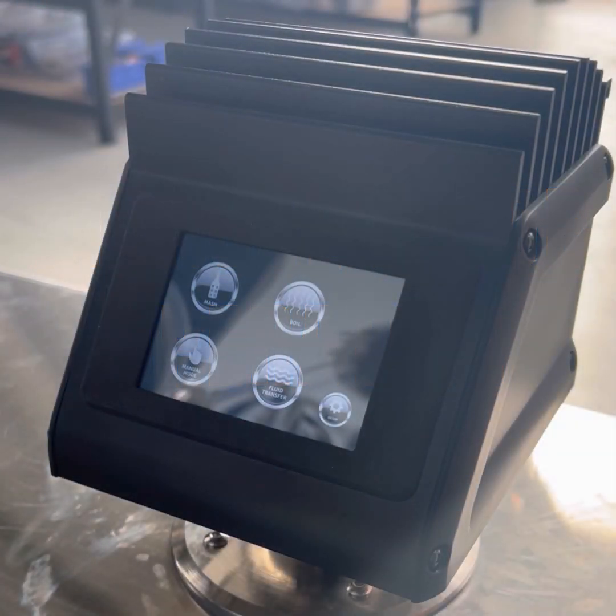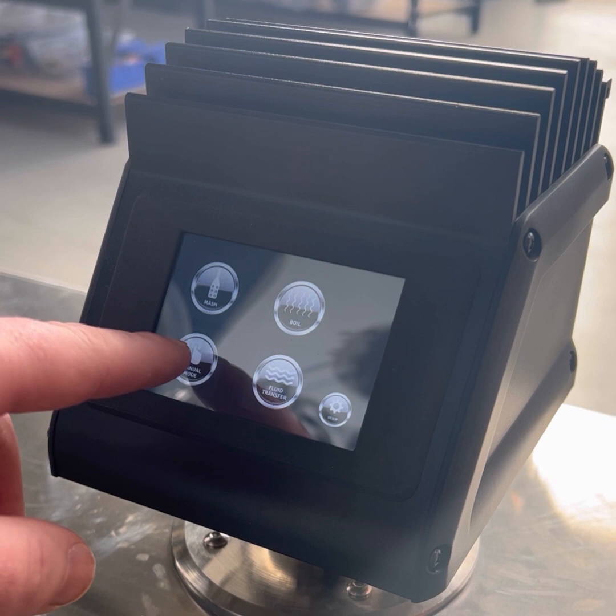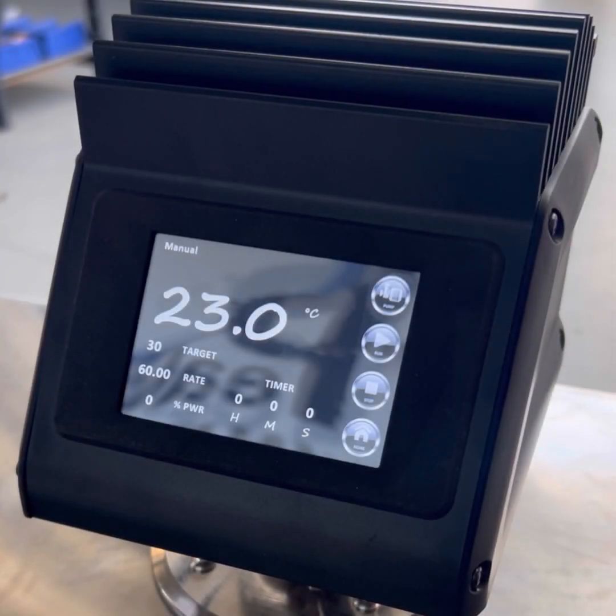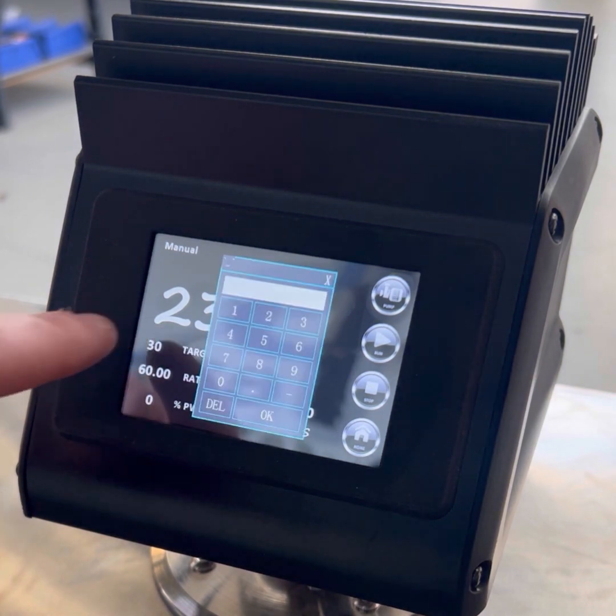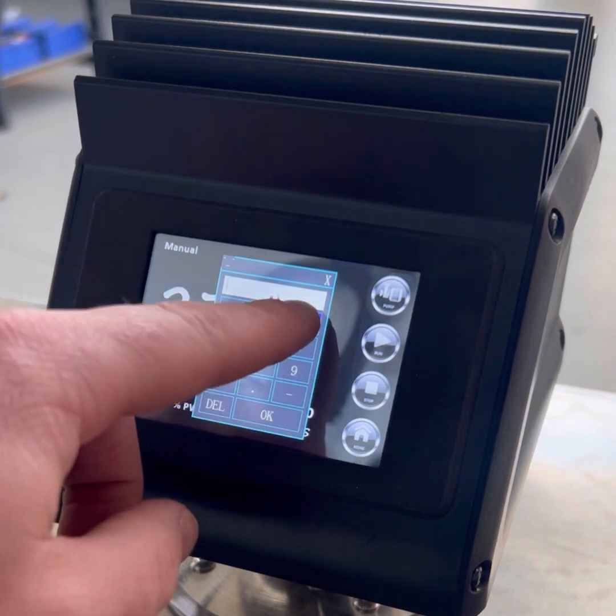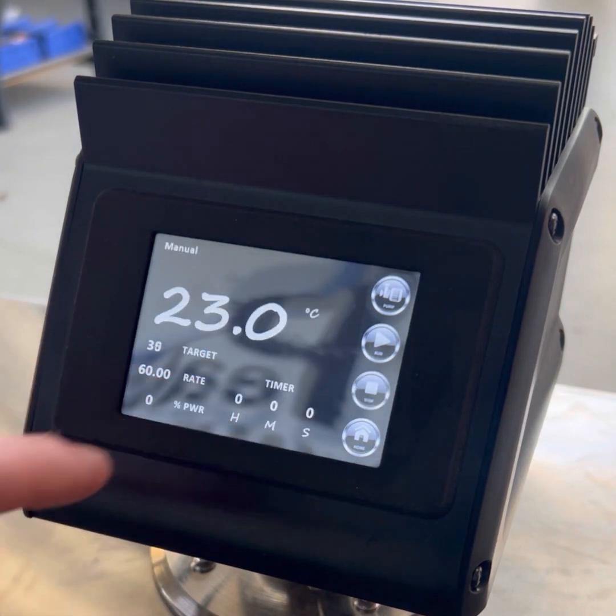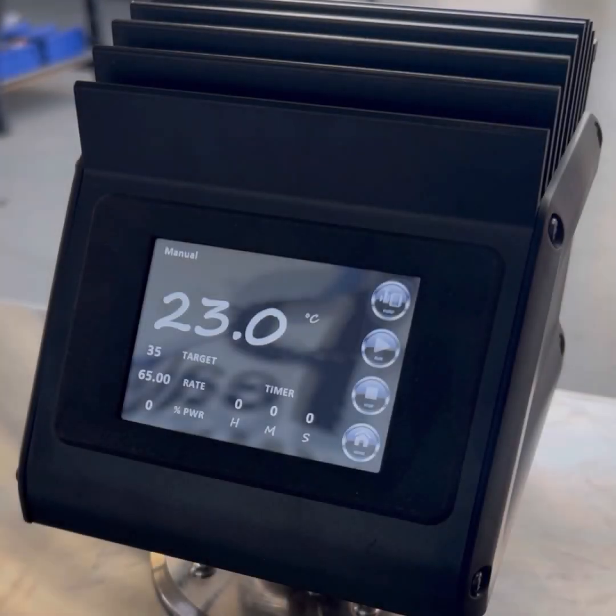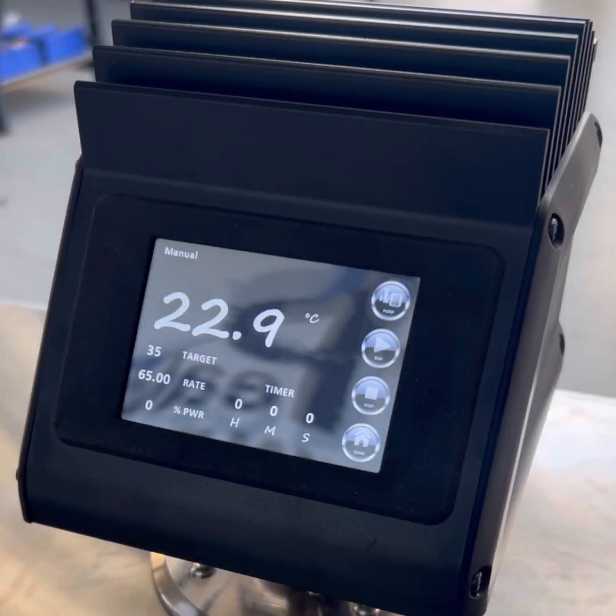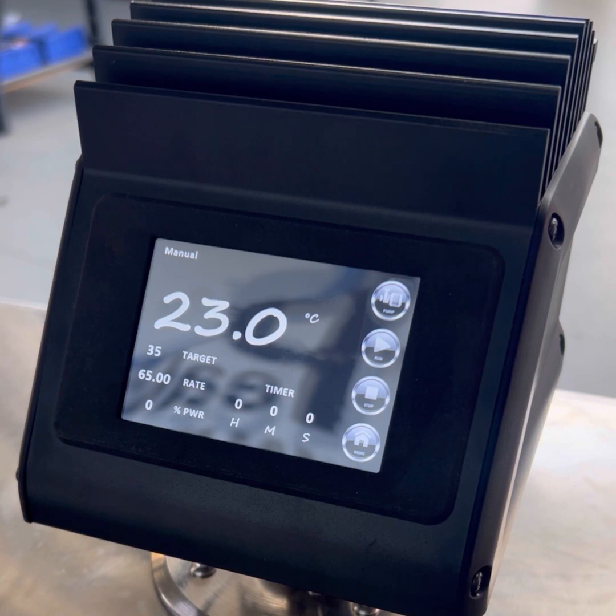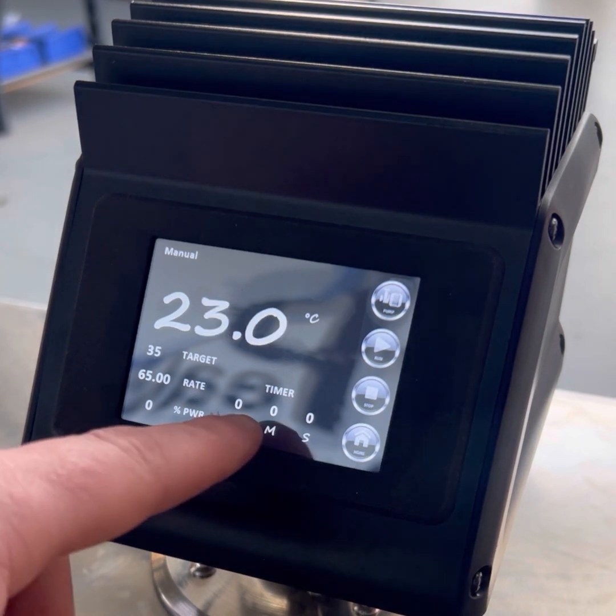The NanoBoss may be operated manually without the need for automated programming. To enter manual mode, select the manual mode icon located on the home screen. Once in manual mode, you may set the desired temperature to maintain by selecting the target number value. Now using the keypad, enter your desired temperature and select OK. As an important safety feature of the NanoBoss controller, the heating element cannot be turned on without first setting a timer. Once the timer cycle ends, your heating element will automatically turn off.